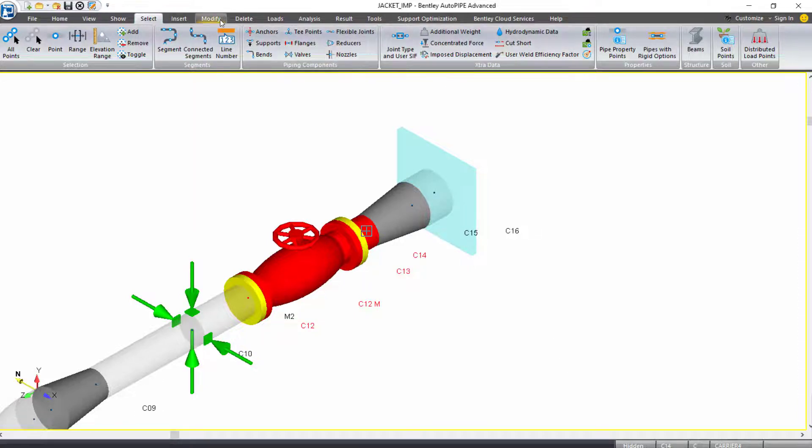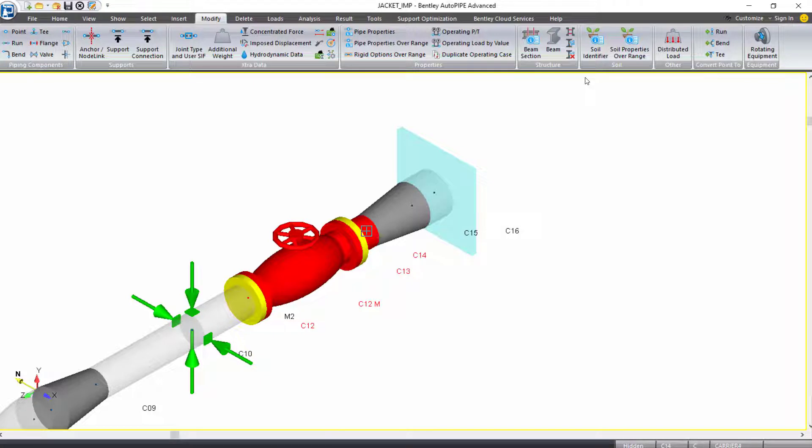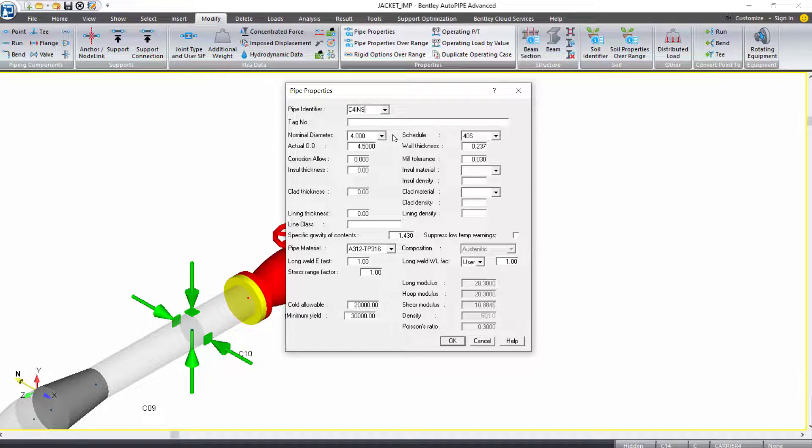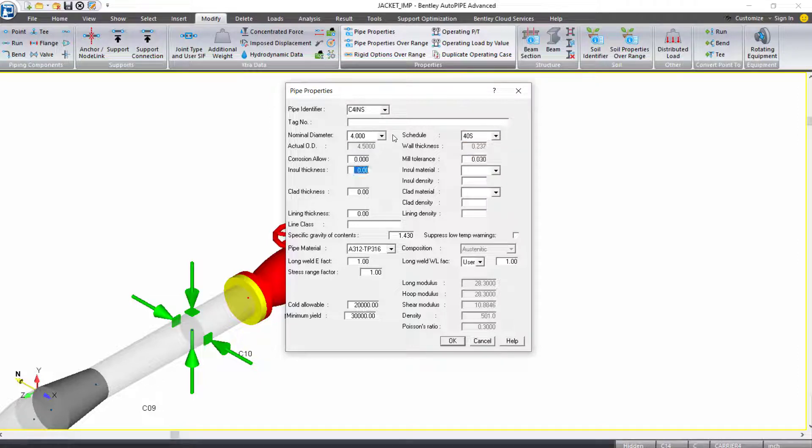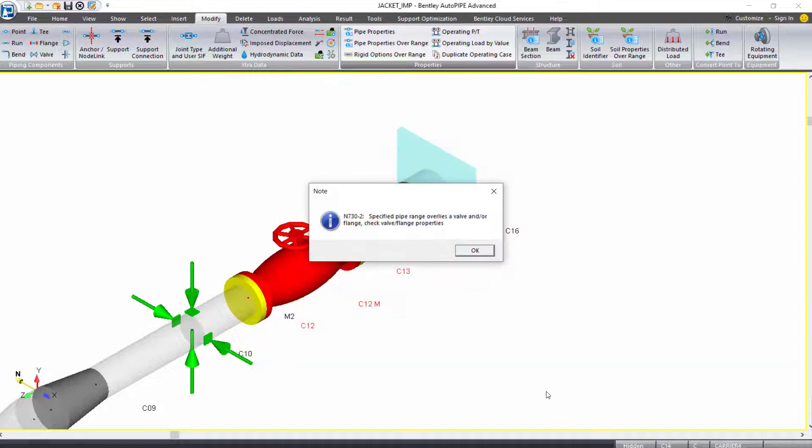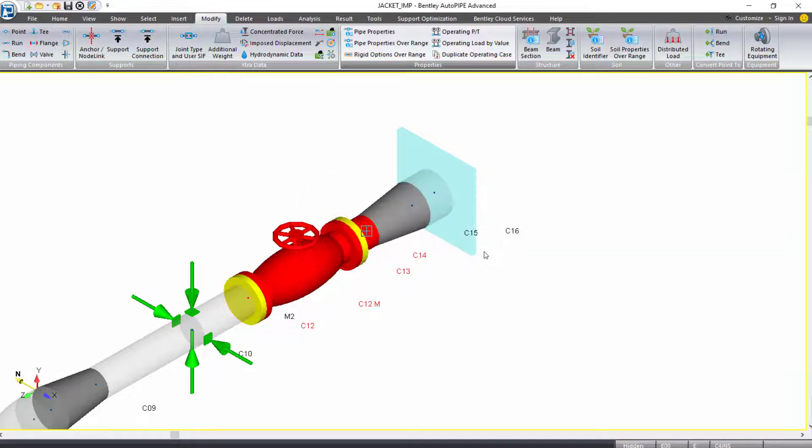I'll select my modify ribbon. Under properties, I'll select pipe properties over range. I'm going to rename this to C4INS to show that it's still my carrier for piping, but I'm adding insulation. I'll tab down to my insulation input, which will be four inch insulation thickness. The material will be calc for calcium silicate, which gives me an insulation density of 11 pounds per cubic feet. With that, I can click OK. It gives me the note about the flange or valve being over this selection, and I can just say OK.